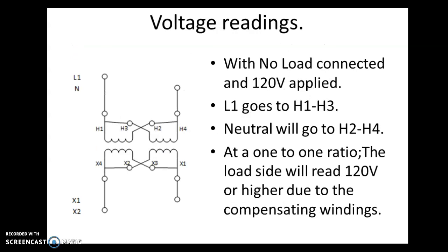For the first portion, where you're going to have no load connected, the voltage readings are as follows. You should see 120 volts applied from line 1. You will be going to H1 and H3. That's a parallel connection. On the neutral side, you'll be going to H2, H4. That is also a parallel connection. Each coil on the primary side will experience 120 volts AC.